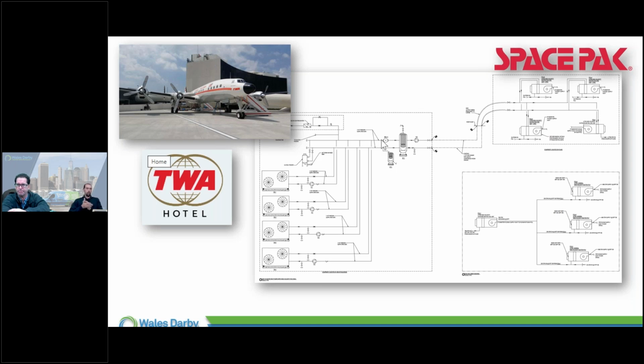Yeah, absolutely, maintenance, high efficiency, right. We got some good long refrigerant lines for an airplane job. Actually, there's not one refrigerant line on this entire job, which is nice with air to water. It's just pumping and piping, like Anthony was talking about. That was PEX tubing running on the ground into the belly of the plane. Actually, it wasn't, it was copper they ran, I lied. But they ran copper, insulated, and all of that stuff, so it's all water lines. We're not limited to refrigerant lines, which is really nice.